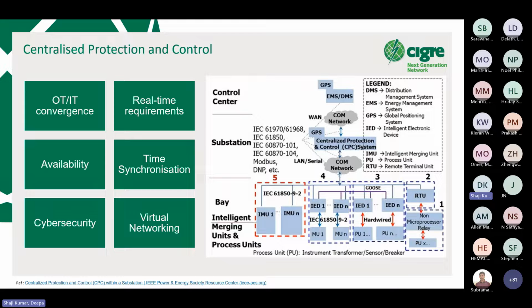Software images with different applications providing monitoring and diagnostics can reside on the same host machine. For example, a set of protection, control, and metering functions of several apparatus residing in a single software image can provide protection of several elements, like distance protection for a line, transformer differential, or a set of directional overcurrent functions, all coming together in a single software image hosted in a COTS device.